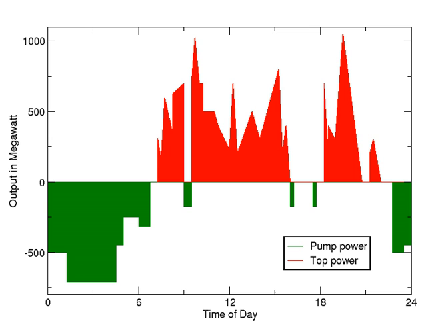Pumped storage provides a load at times of high electricity output and low electricity demand, enabling additional system peak capacity. In certain jurisdictions, electricity prices may be close to zero or occasionally negative when there is more electrical generation available than load to absorb it. Increased wind and solar generation will increase the likelihood of such occurrences. It is particularly likely that pumped storage will become especially important as a balance for very large-scale photovoltaic generation. The high non-firm renewable electricity penetration in some regions supplies 40% of annual output, but 60% may be reached before additional storage is necessary.